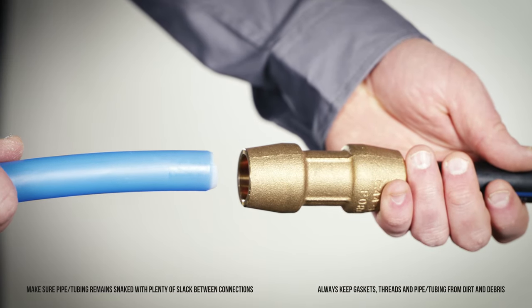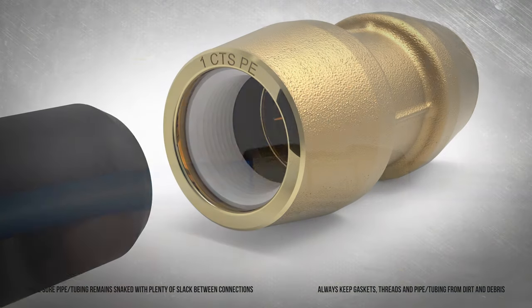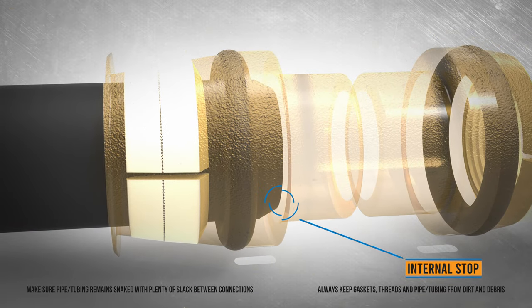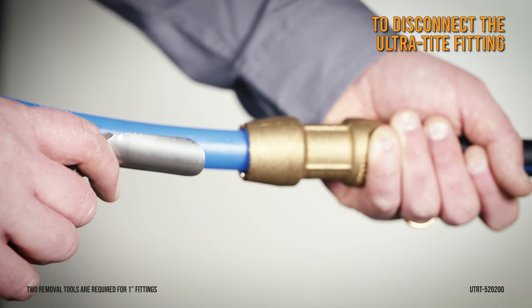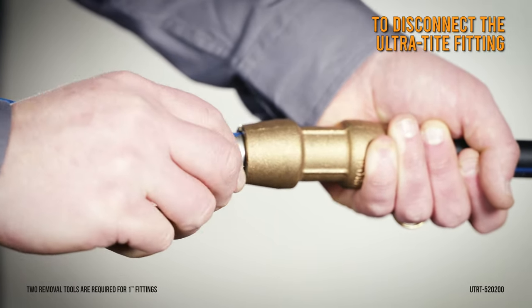Align the pipe or tubing with the fitting and push it straight into the fitting all the way through the grip ring and the O-ring until it reaches the internal stop to ensure a complete and well-supported connection. Ultra-Tite fittings can be removed and reused; a removal tool is required to disconnect the Ultra-Tite fitting. Slide the tool between the pipe or tubing and the fitting to relieve the grip engagement, and then pull the pipe or tubing from the fitting.